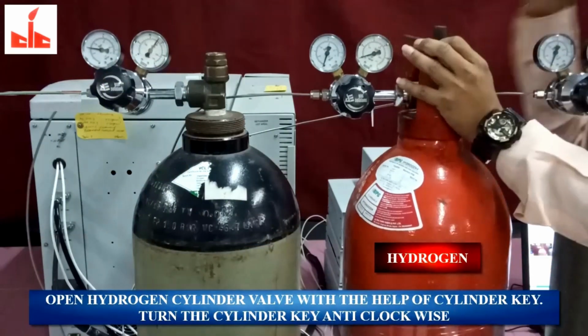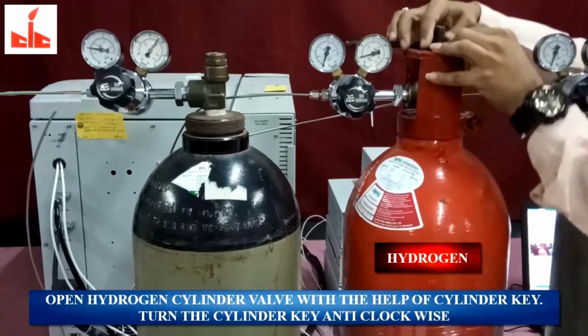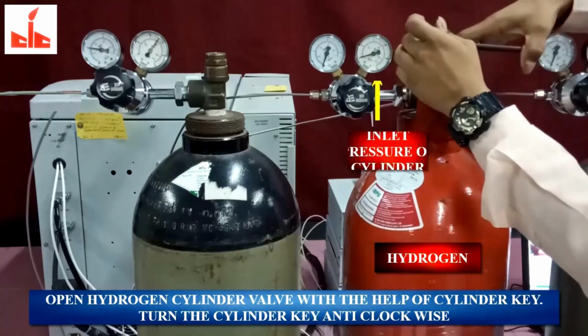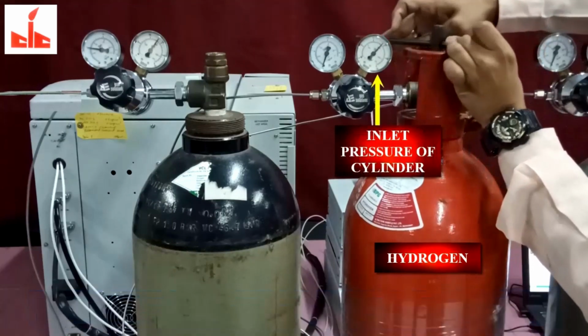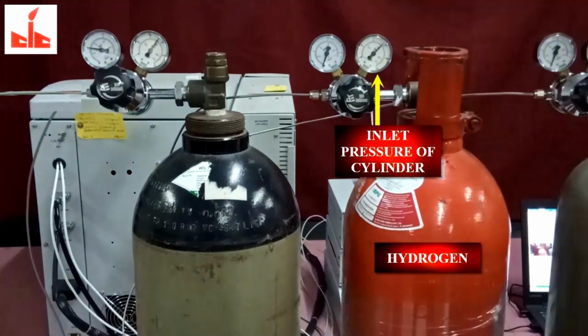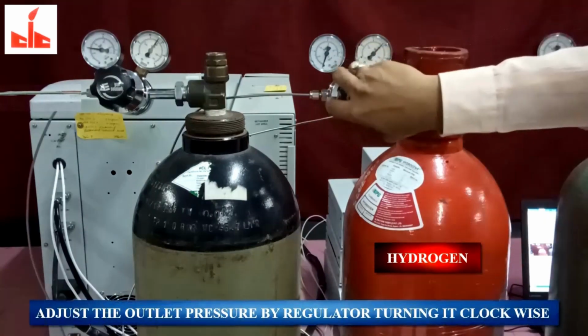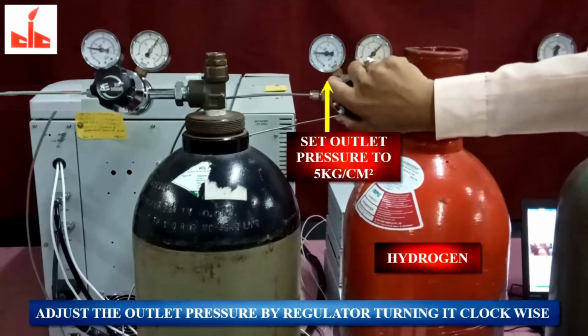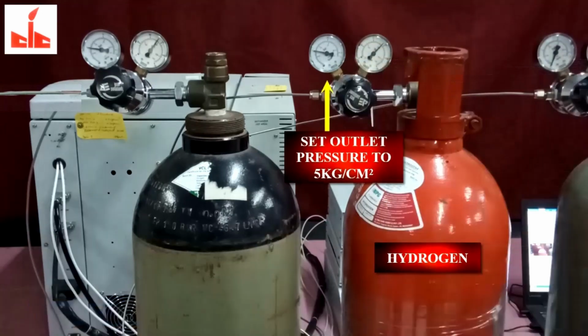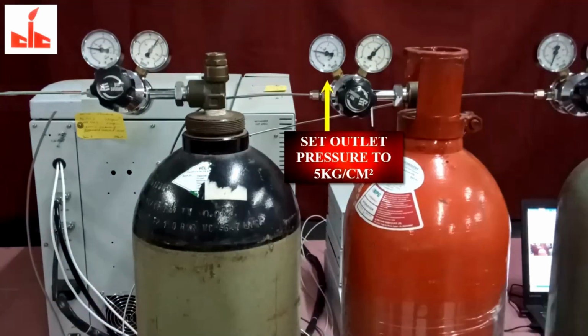Open hydrogen cylinder valve, with the help of cylinder key. Turn the cylinder key anti-clockwise to open it. Right side pressure gauge shows the inlet pressure of cylinder. Adjust the outlet pressure by regulator, turning it clockwise and set it to 5 kg per centimeter square.